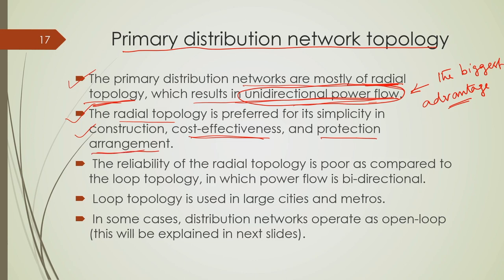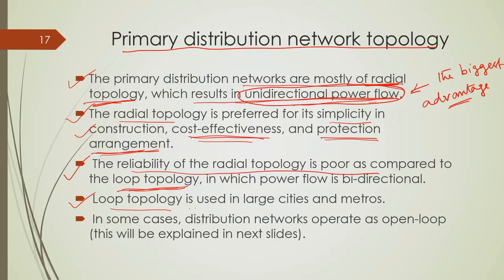So, these are the advantages of this radial topology. Okay. It is the simplest form of network and it is preferred particularly in distribution networks. For the simplicity in construction, cost effectiveness, it is for economy, it is the best option, and also the protection is less complicated, in fact, a very simple protection arrangement. Okay. But the reliability is poor for this radial topology as compared to the loop topology. I will have some single line diagram in which I will explain why it is so. Okay.